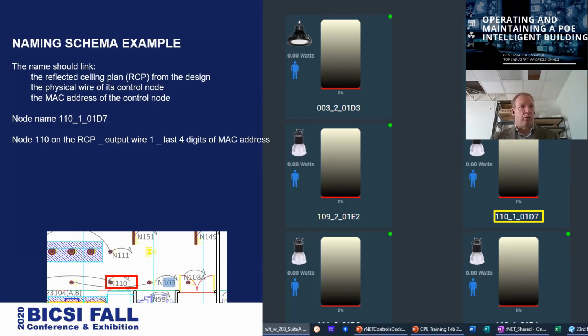So essentially we've unified the design intention, the physical installation, and the software connection between the two. In this example, I've got node 110, which is a light fixture, physically wired to output 1, on the node with MAC address ending in 01D7.